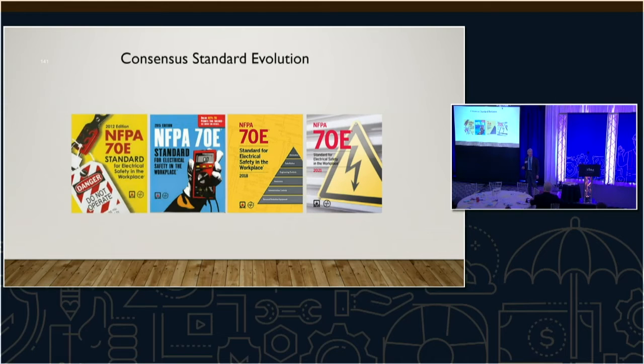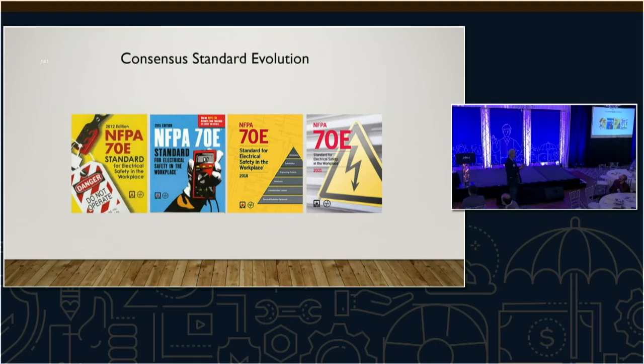There's a separate requirement for electrical voltage zero voltage verification when you're talking about lockout, tagout, or control of hazardous energy that's electrical. That's a big difference you need to understand, because if your lockout, tagout procedure is simply press the start button to verify the power's off, and somebody's changing out a motor with live wiring, they could get shocked. They need to verify zero energy with a meter, period. That's the law. It's just not in the lockout tagout standard, which is OSHA 1910.147 - it's in the electrical part. So there's an emphasis on using a meter and being trained on it.